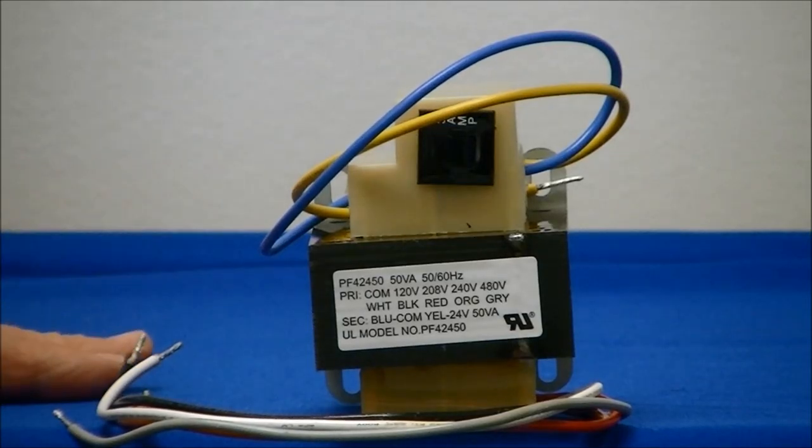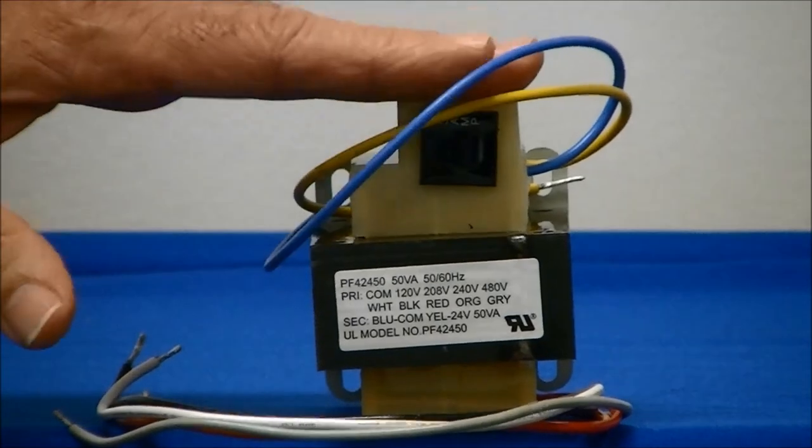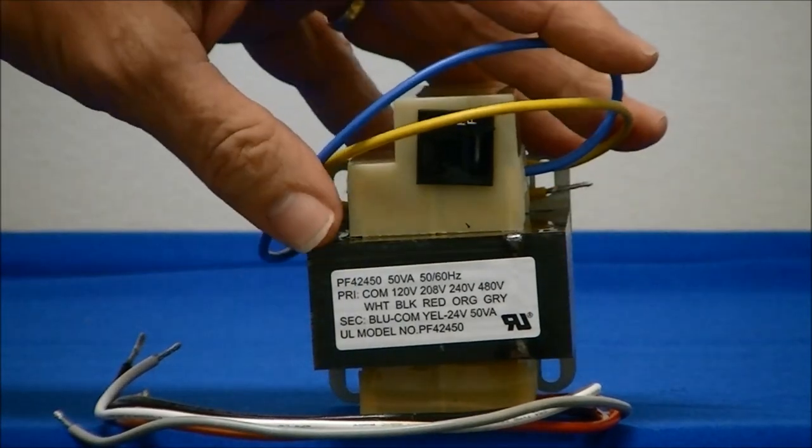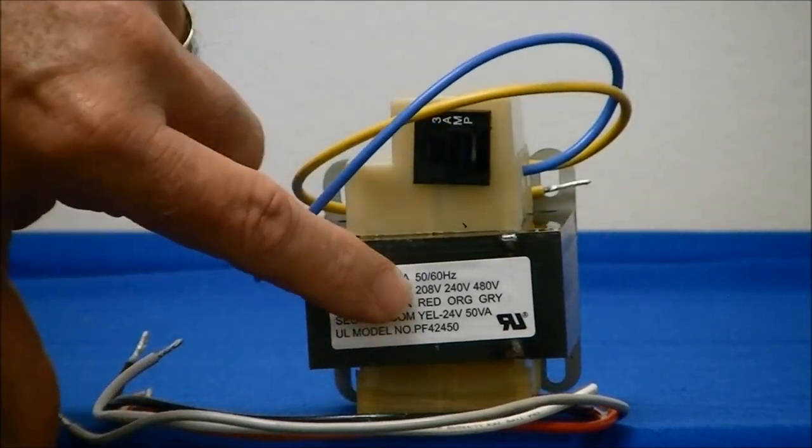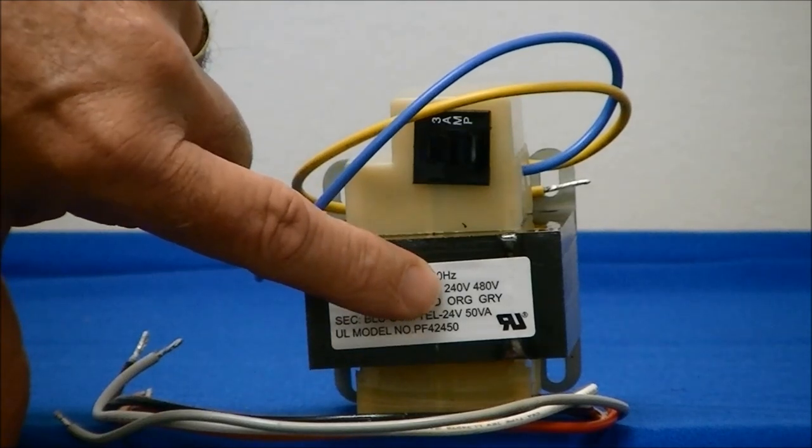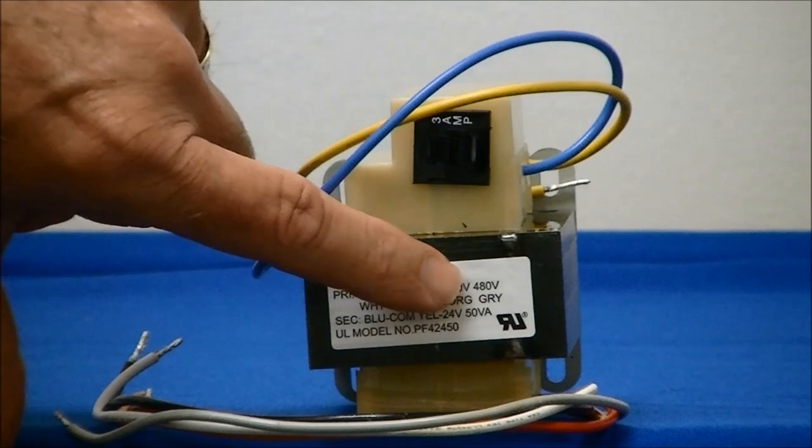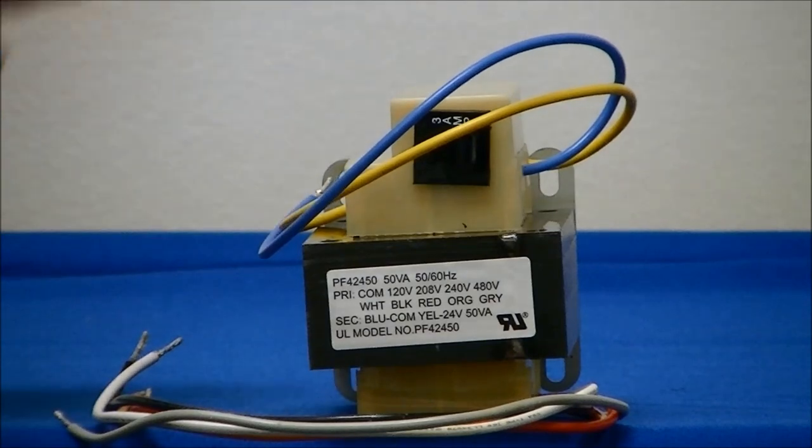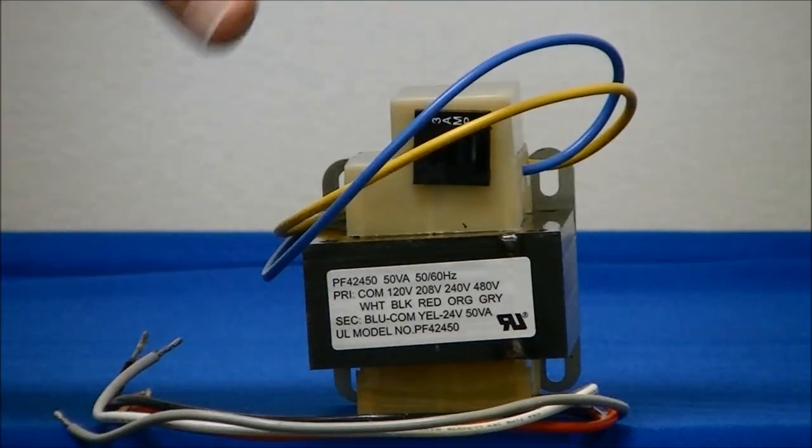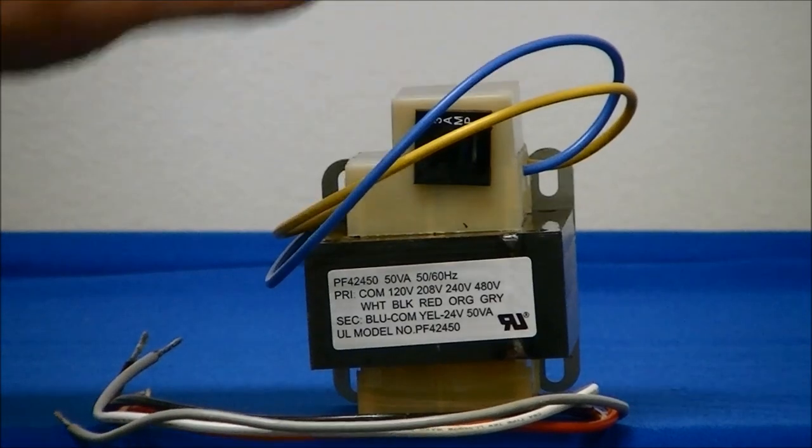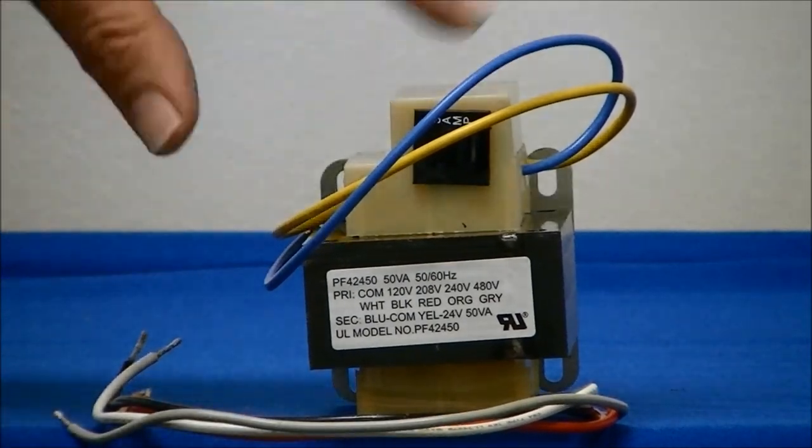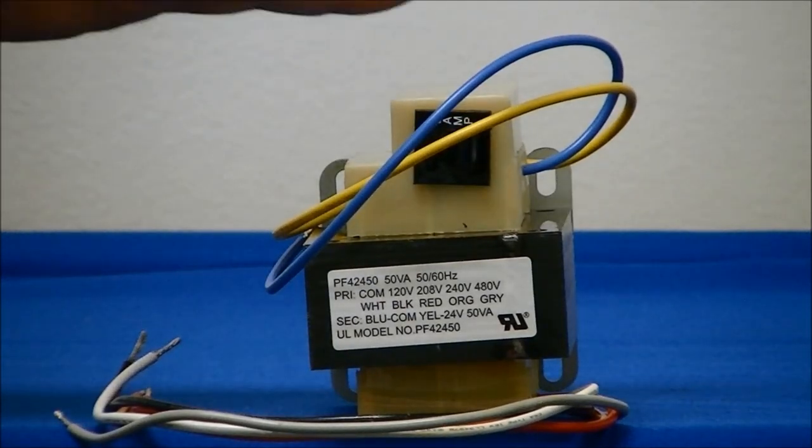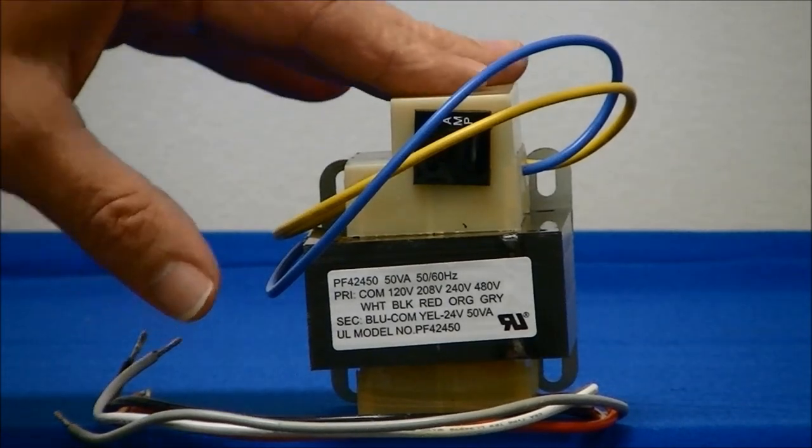The second transformer can also be used on primary voltage of 120. But in addition to that, it's suitable for 208 volts, 240 volts, and 480 volts. So this particular transformer is not only capable of converting from 120 volts, but you can use it for multiple voltages. So it's a very versatile transformer. Now these types of transformers are more expensive, but it's a great transformer to carry on the truck for multiple applications.